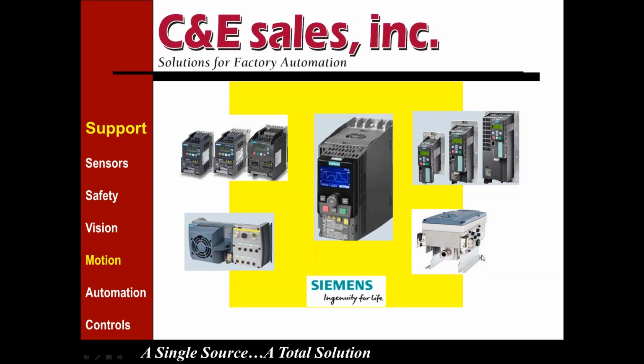Below that, we have a wall mount or surface mount G110M drive. These are specifically designed to bring 480 volts in one side, daisy chain it out the other side, and these are perfect for connecting together on a 480 volt chain on the side of a conveyor. The motor lead comes out the bottom here with a cable gland giving you IP65 protection. And then to the left is a G120D. This is a high performance G120 drive, again an IP65 format, and these IP65 drives do not have to go in the panel, which is getting very popular nowadays. So this first slide just illustrates all the different choices we have just on the VFD line.